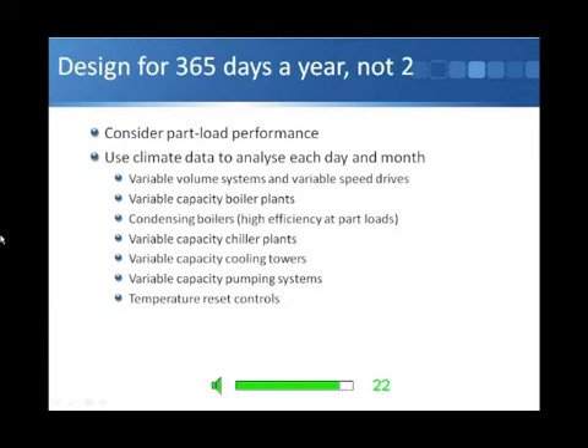I think one of the points I would make, of course, is that we're looking at part load performance most of the time. In the UK here, we design heating systems for the coldest day of the year, which might be today, I suppose. But it only occurs for 1 or 2 days a year by definition. It's the design day. Most days, we have a 240-day heating season, so 220 of those days, the temperature is more likely to be between 5 and 15 degrees C. And that's what happens most of the time. So we need to think about part load operation as well as peak load.